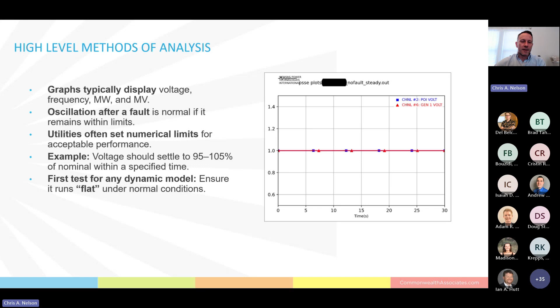So this is an example of a voltage disturbance on the system, and this isn't so much a fault. This is a small site with the utility point of interconnection running a little higher. The point of interconnection is set to 102% of nominal voltage for the duration of the test, and you can see that's the blue line in this graph. So it goes a little bit higher and then it settles back down to 102% and it just stays there.